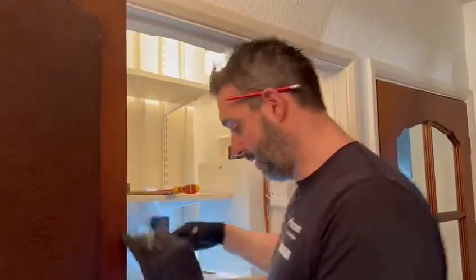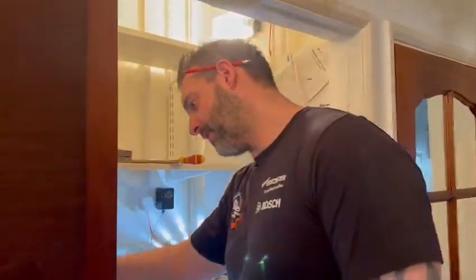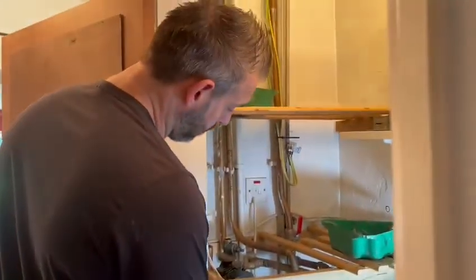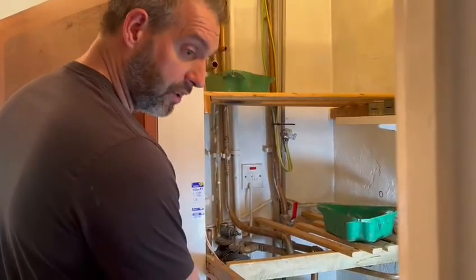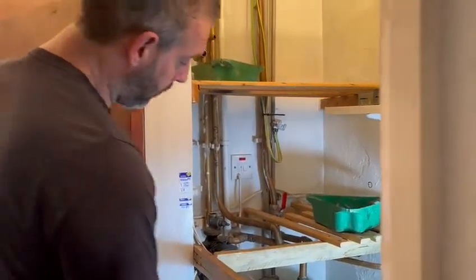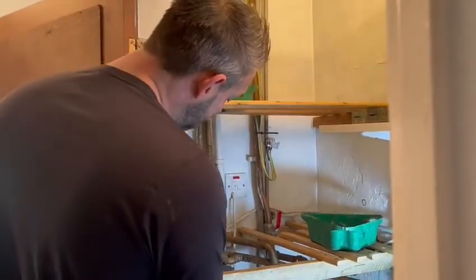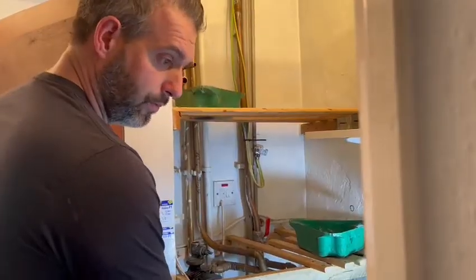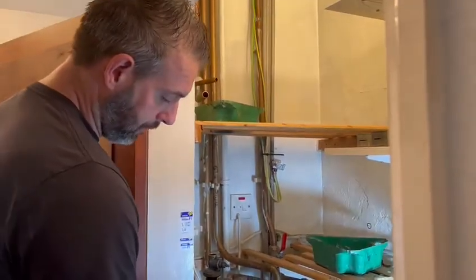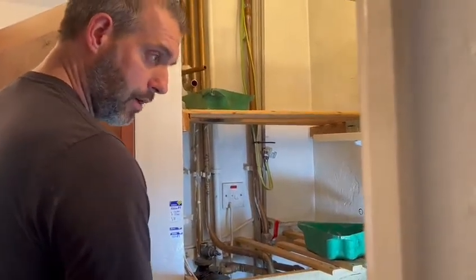And this is what we've got here — blocked pipework, absolutely solid blocks. This should have been attended to on installation. Obviously it wasn't — very poorly installed. Worcester turned the boiler off and condemned it. It's only six months old and it's just endless external problems. Obviously if this happened and we installed the boiler, we would have sorted all this out on the install — hence the boiler installation specialist. We would have left the customer with a working boiler and system. But obviously this hasn't been done properly, so we've been called in and we'll get it all up and running.